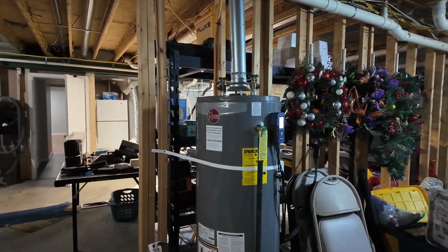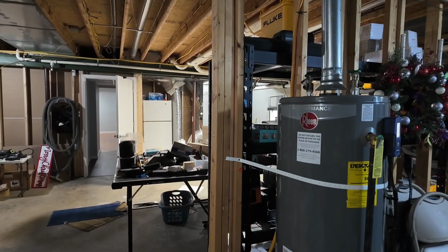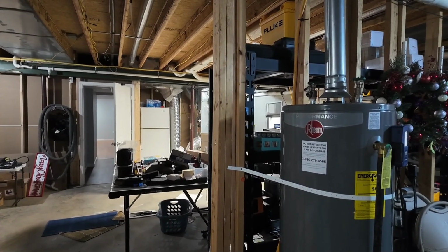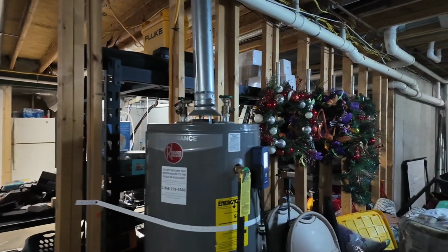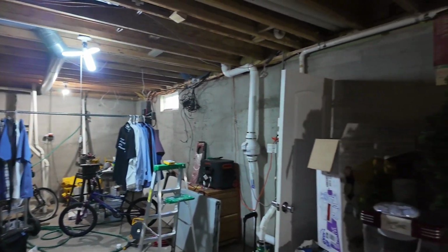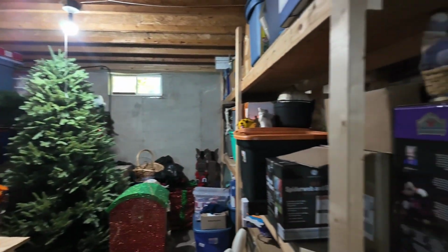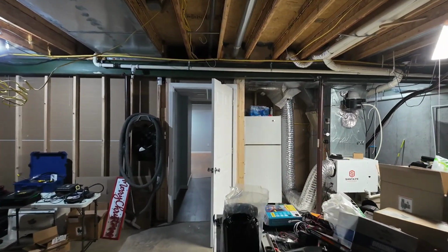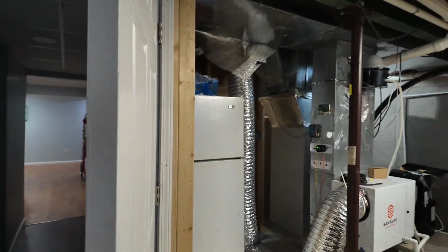Item number 3 on combustion safety testing says, can it identify the specific location and boundaries of the primary CAZ and any secondary combustion appliance zones? Well, this is the water heater, and the CAZ is the combustion appliance zone, the area that the combustion appliance is located in. In this particular case, it's everywhere from this door in the basement inward.